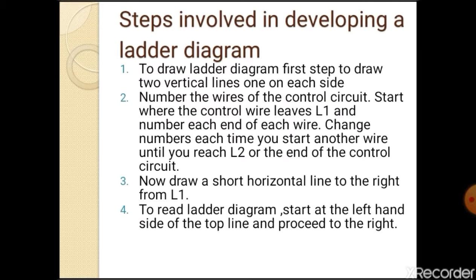Steps involved in developing a ladder diagram. To draw ladder diagram, first step: draw two vertical lines, one on each side. Second, number the wires of the control circuit. Start where the control wire leaves L1 and number each end of each wire. Change numbers each time you start another wire until you reach L2 or the end of the control circuit. Third, now draw a short horizontal line to the right from L1. Fourth, to read ladder diagram start at left hand side of the top line and proceed to the right.